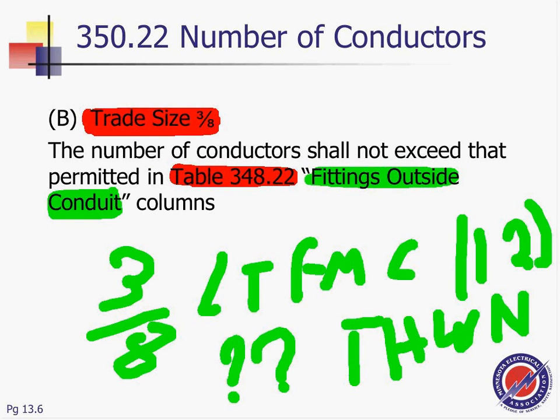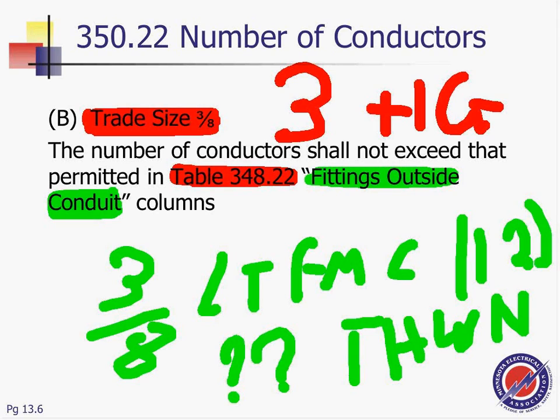Any questions about how to use this table? For liquid flexible only, you ask yourself, are fittings inside or outside? They have to tell you, because for flex you can put some fittings inside and some outside. For Liquidtight, they're all outside. Based on our analysis here, we found it's going to be 3 conductors plus 1 conductor ground, if they ask you about the ground. Any question about using this table?